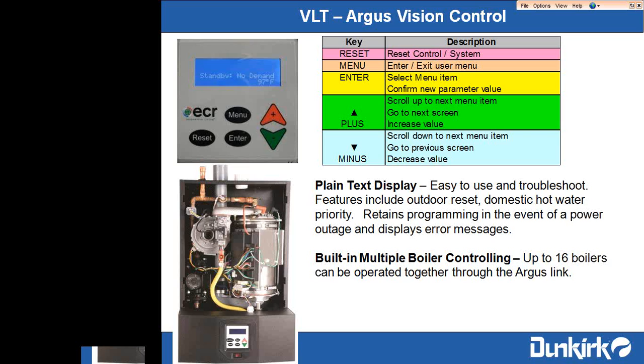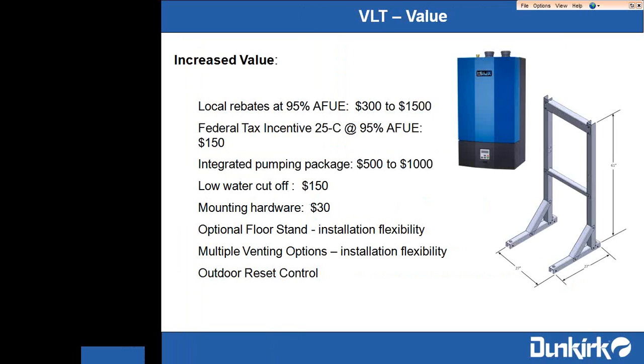In addition, for your contractors that do commercial work, we see as an industry more and more modular or multiple boiler systems going in for commercial applications as opposed to the older, larger, inefficient forced draft boilers that are out there. And again, currently we make this product as high as 299,000 BTUs. That Argus controller can modulate up to 16 Helix VLT boilers without needing any additional sequencing controls. So there's a lot of functionality to the control itself.